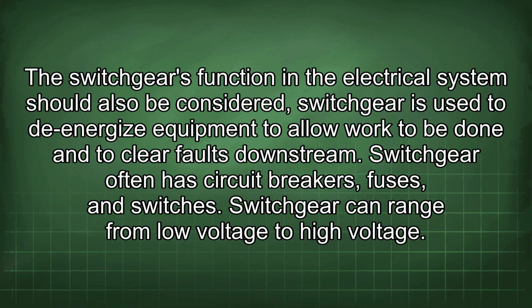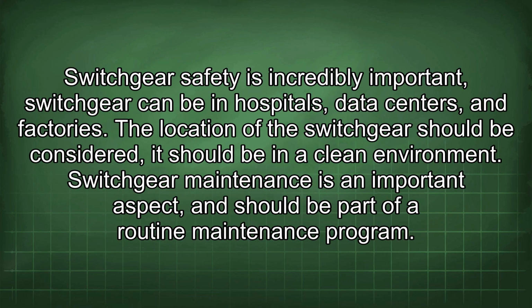The switchgear's function in the electrical system should also be considered. Switchgear is used to de-energize equipment to allow work to be done and to clear faults downstream. Switchgear often has circuit breakers, fuses, and switches. Switchgear can range from low voltage to high voltage. Switchgear safety is incredibly important. Switchgear can be in hospitals, data centers, and factories.